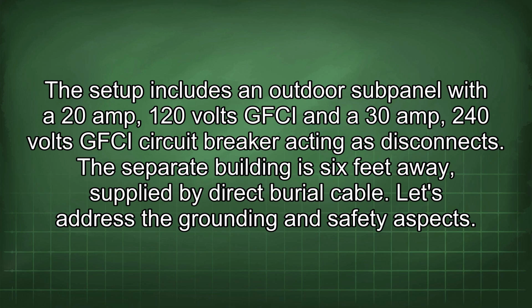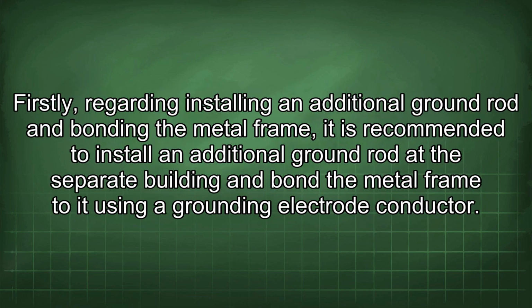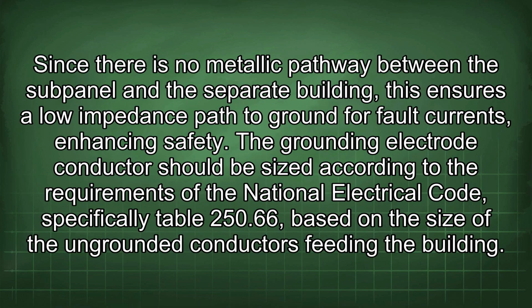The separate building is 6 feet away, supplied by direct burial cable. Let's address the grounding and safety aspects. Firstly, regarding installing an additional ground rod and bonding the metal frame, it is recommended to install an additional ground rod at the separate building and bond the metal frame to it using a grounding electrode conductor. Since there is no metallic pathway between the subpanel and the separate building, this ensures a lower impedance path to ground for fault currents, enhancing safety.